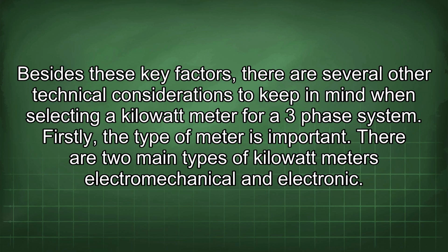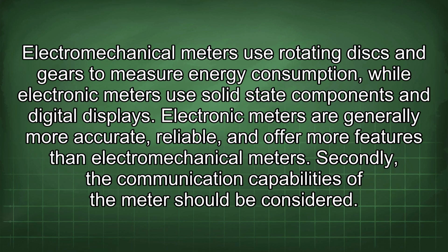Besides these key factors, there are several other technical considerations to keep in mind when selecting a kilowatt meter for a three-phase system. Firstly, the type of meter is important. There are two main types of kilowatt meters: electromechanical and electronic. Electromechanical meters use rotating discs and gears to measure energy consumption, while electronic meters use solid-state components and digital displays. Electronic meters are generally more accurate, reliable, and offer more features than electromechanical meters.